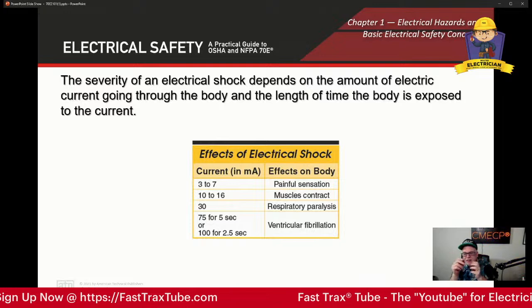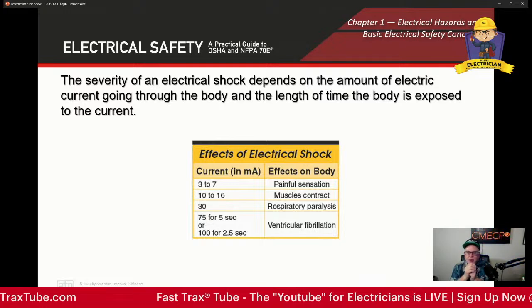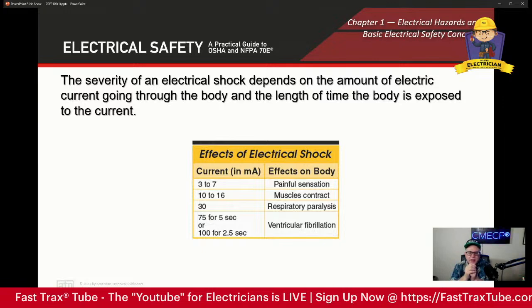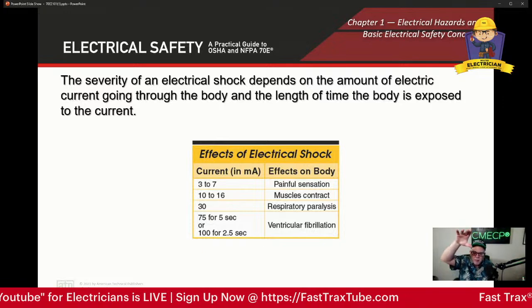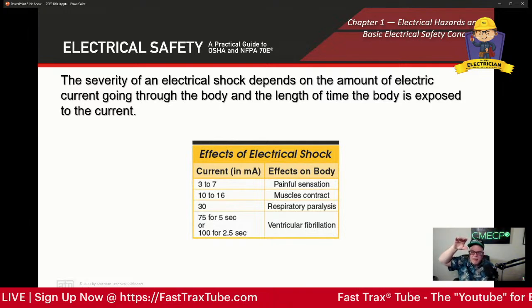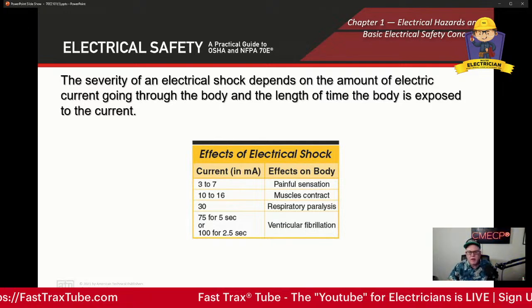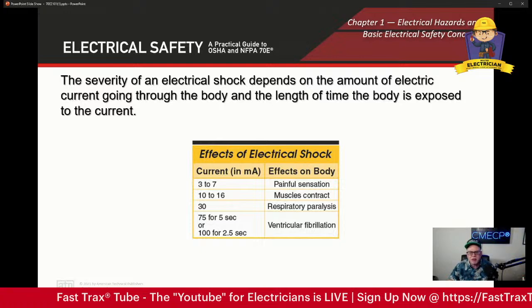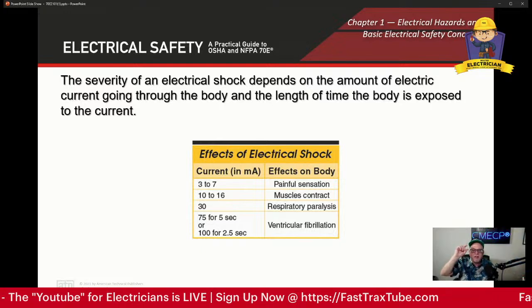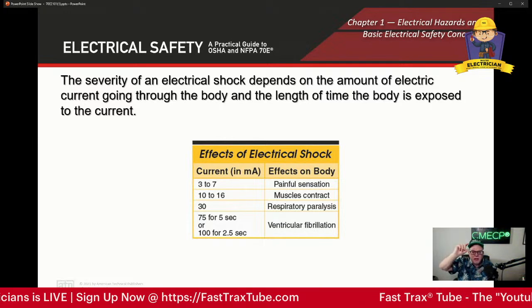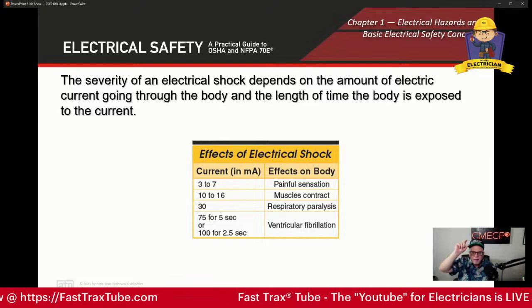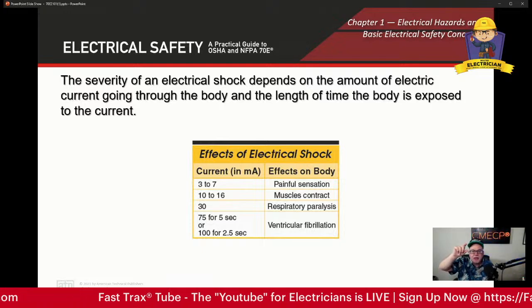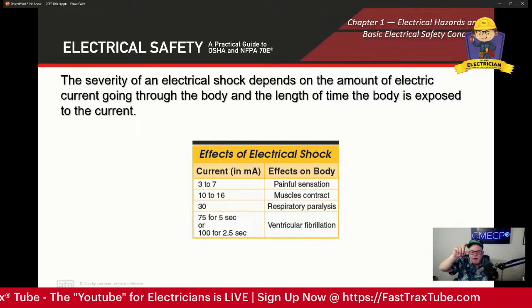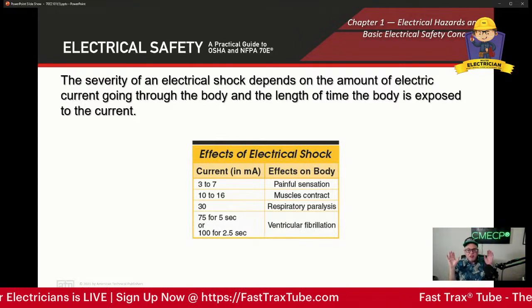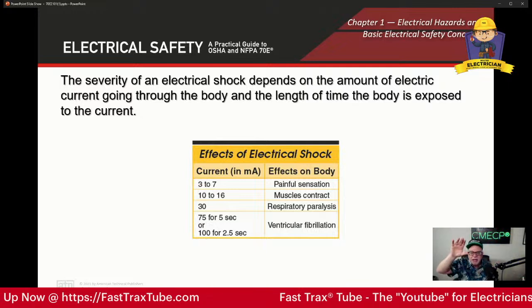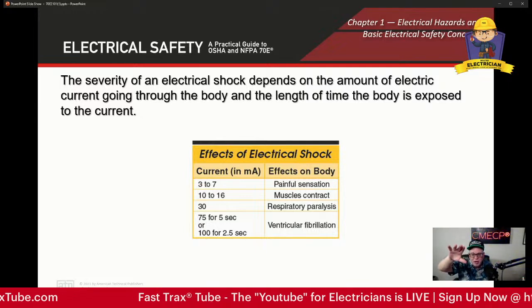So when they contract, let's say you're crawling in a crawl space and maybe a metal pipe is energized because somebody bonded improperly, and you put your hand up on this pipe to support yourself as you're trying to get under it, that's all it takes. I can tell you of an incident where an individual and his helper were both electrocuted by that scenario, by these energized metal pipes in a crawl space because somebody improperly bonded the lines thinking they were required to, but they did everything improperly and the pipes were energized. Everything was fine and dandy until that gentleman came in contact with it, and then his helper reached over to try to help, and they were both electrocuted.